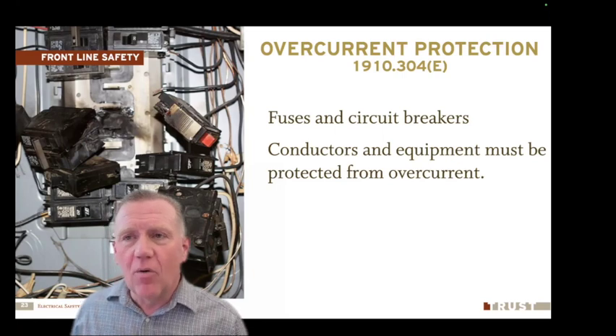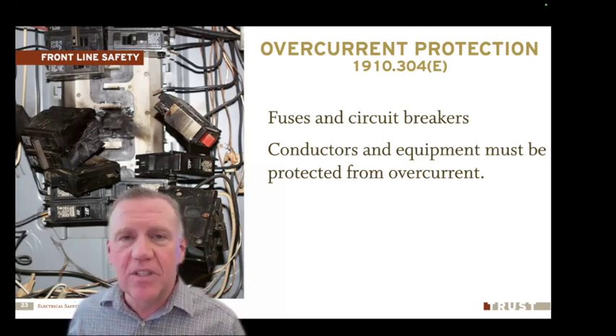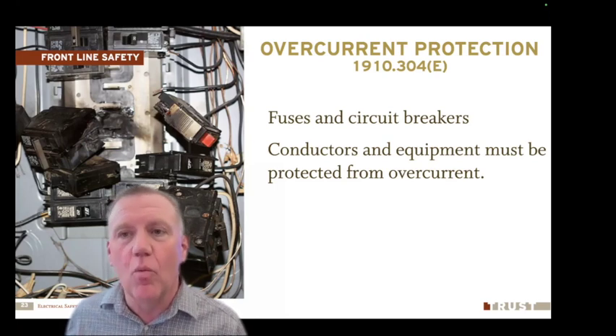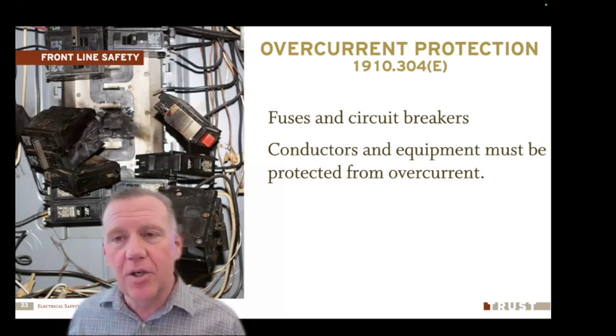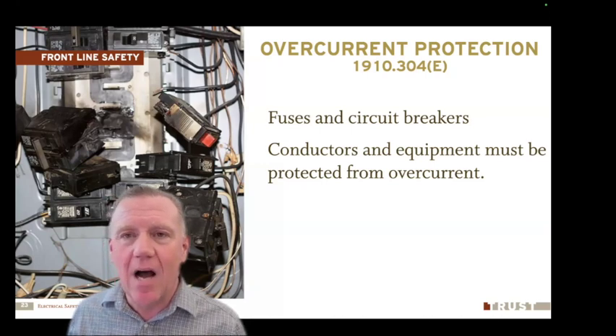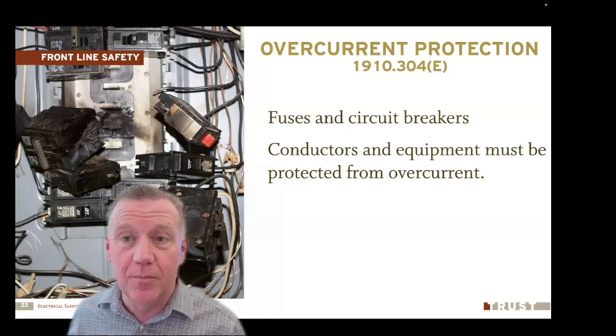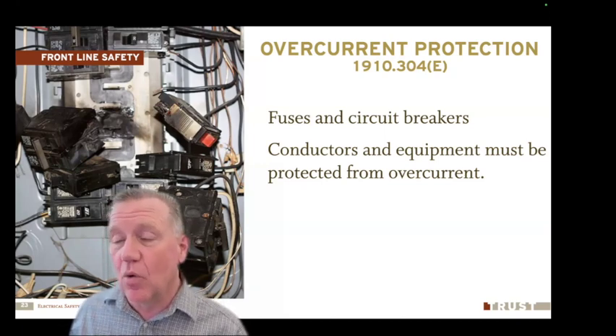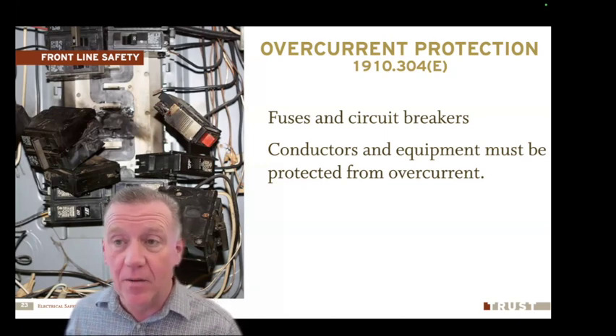It's plenty to kill you. What are these overcurrent protections, the circuit breakers, designed to protect? They're designed to protect the conductor, the wires that come out of there. We don't want to draw so much current that those wires get hot and burn our buildings down, melting the insulation off the wires and causing a fire.